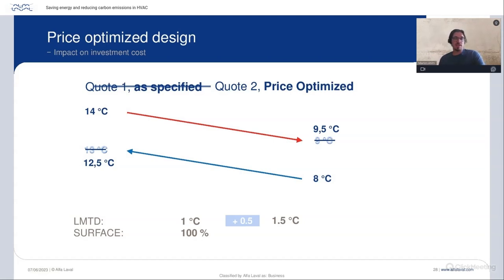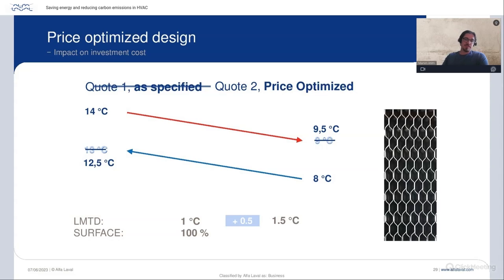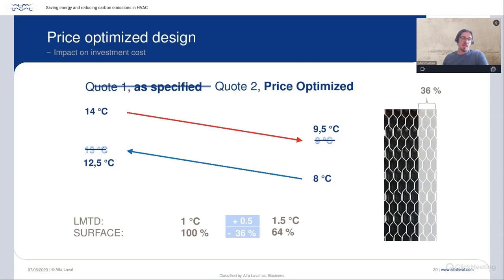So why is this implemented in the market? If we have the plate pack or the surface area of the heat exchanger, by shifting the temperature a little bit with this half a degree, the demand for surface area in a heat exchanger would be reduced by 36%. And this is, of course, the reason. The equipment becomes cheaper to purchase and you can give a better price-optimized quote to a customer.